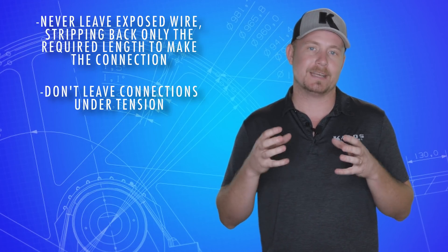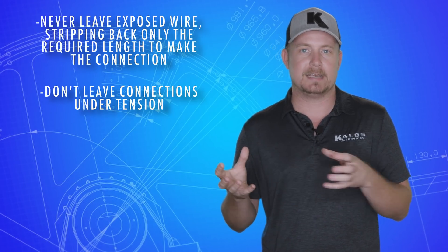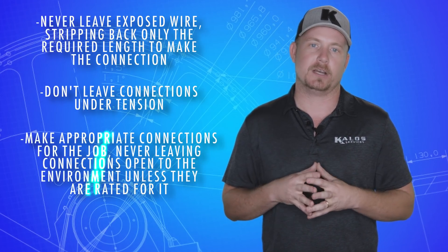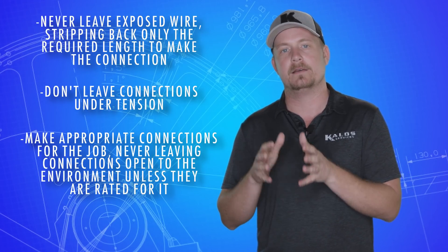Don't leave connections under tension, meaning where they want to pull off. Use straps and zip ties to keep the tension away from connections so that they aren't left under a pulling or disconnecting force. Make appropriate connections for the job. Never leave the connections open to the environment unless they're rated for it.